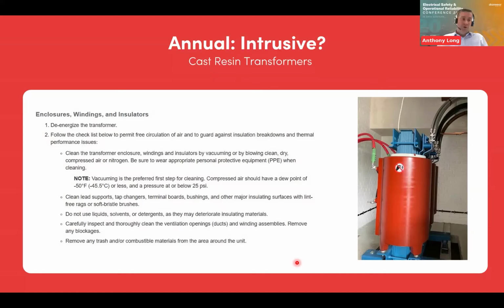And obviously, I'm constantly running short of time on this webinar. Also, linking back to condition 1, we mentioned it before in the NFPA 70B standards, condition 1 is 60 months, so 5 years. But the equipment might have never been used much at all, and it might be 5 years old. In actual fact, because it's never been used, if it's not had any mechanical checks in that period of time, you may then come to use it, classing it as normal operating condition. In actual fact, you might be waiting for an absolute massive catastrophic failure because the mechanics haven't ever been used in that period of time.